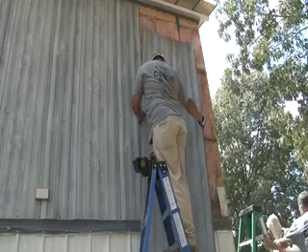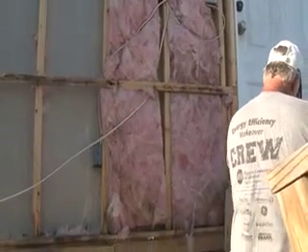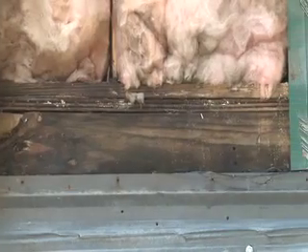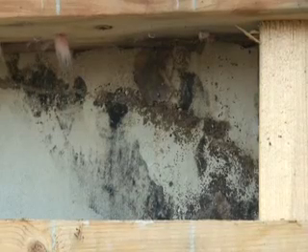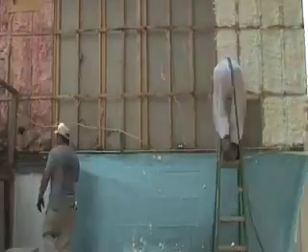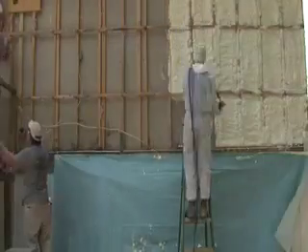Our crescendo this week was what we did to the outer walls. Our makeover team removed the outer panels and exposed the root cause of all the air infiltration. It also exposed evidence of recurring water issues caused by condensation from the old aluminum windows and improperly installed fiberglass insulation. So we removed all the old insulation, and Summit Builders installed Sealant Tech foam into the stud cavities.